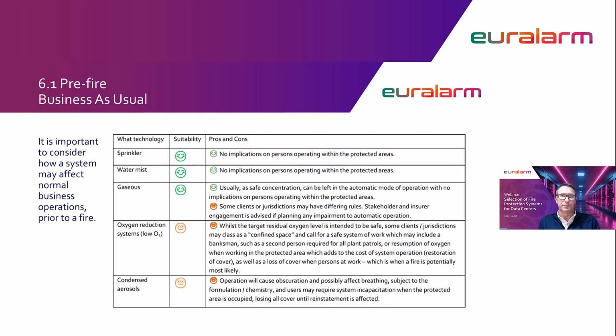Starting with business as usual. I speak from experience where a client had an oxygen reduction system for their grey space. Initially this seemed great, but their safe system of work meant each plant patrol, done 2 times per day, required 2 people instead of 1. Due to the low oxygen, they had the plant inspecting technician accompanied by a banksman who stood in the doorway with the door held open. Not only was that double the labour cost, but the door being open caused a compromise to protection. Furthermore, restoring the protection drank loads of electricity, which was an appreciable sum.